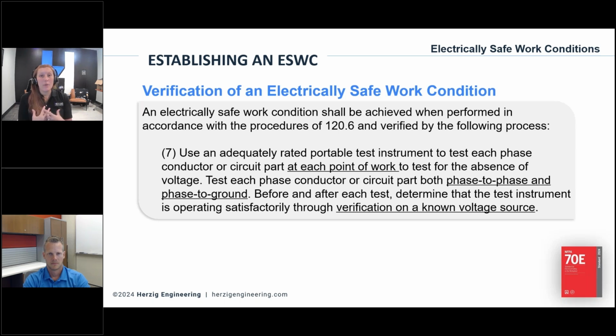So if you're going to open up and expose any electrical conductors or circuit parts at 50 volts or greater, by and large, sometimes there's unique situations, but 50 volts and greater, then you have to be able to use a meter to test for absence of voltage. That is truly when you know it's safe. There are too many stories out there where people shut it off and lock it out, and then they get to work and something's still energized, and they may or may not survive to tell the tale themselves. So this is a super, super critical point.